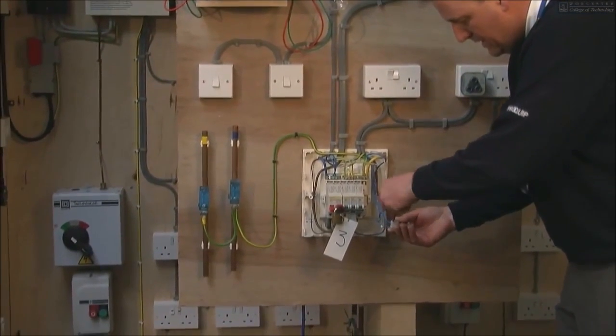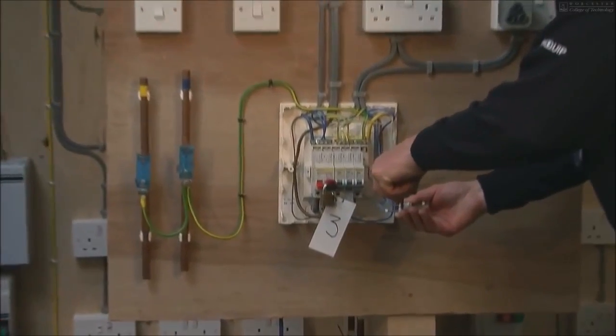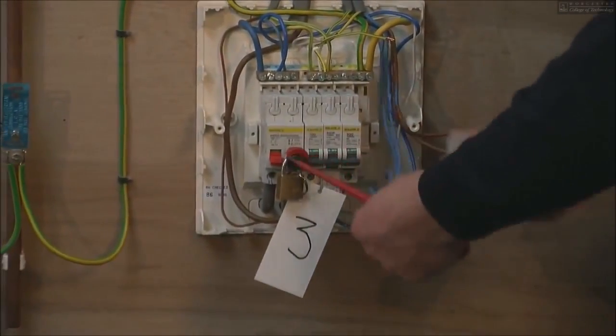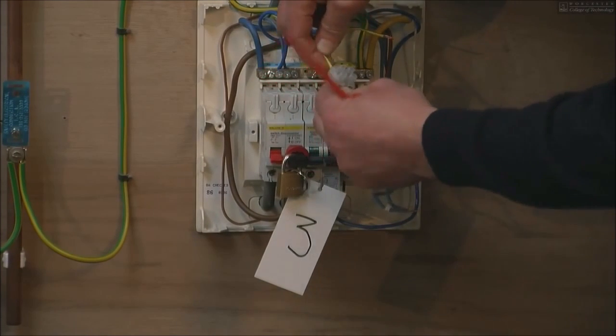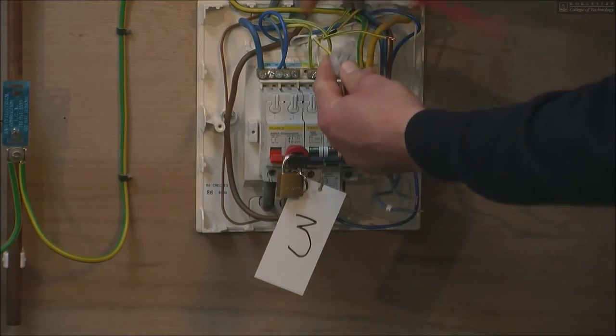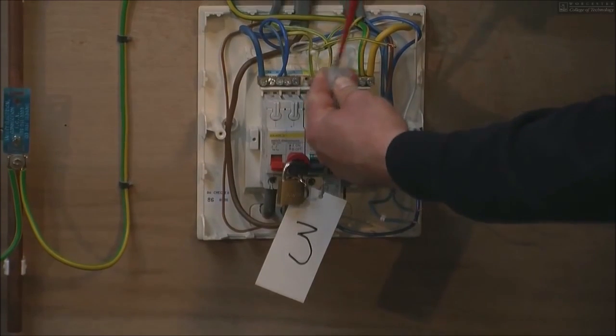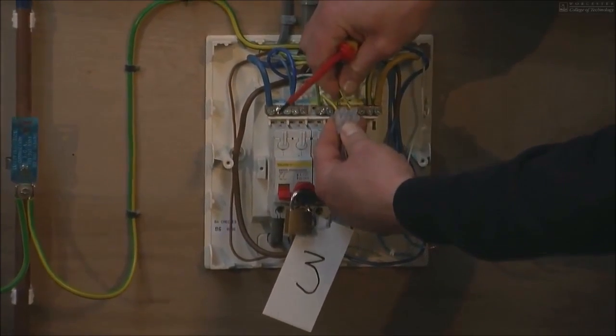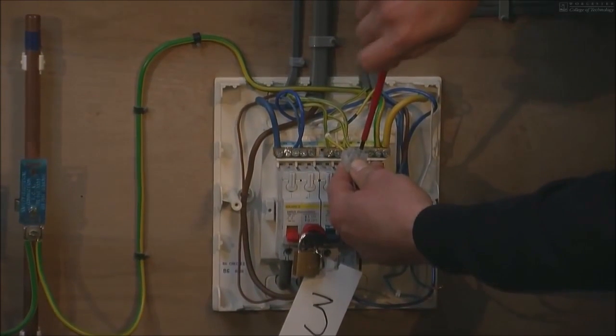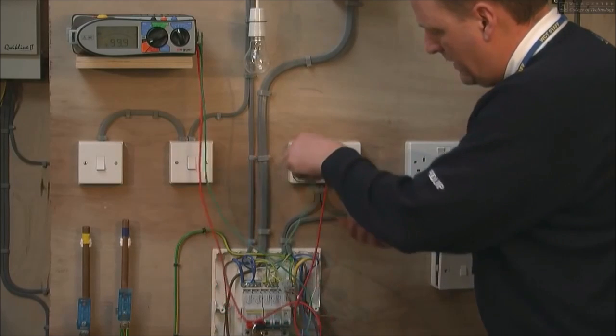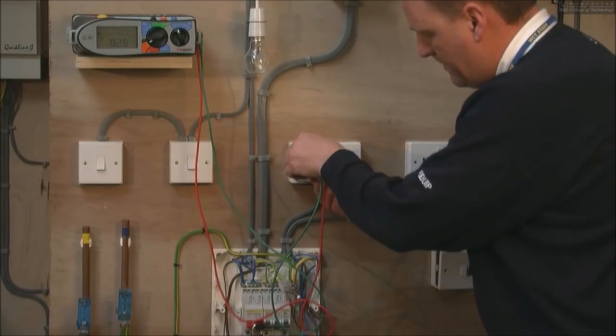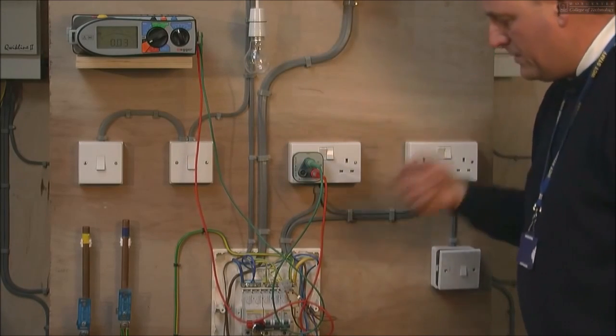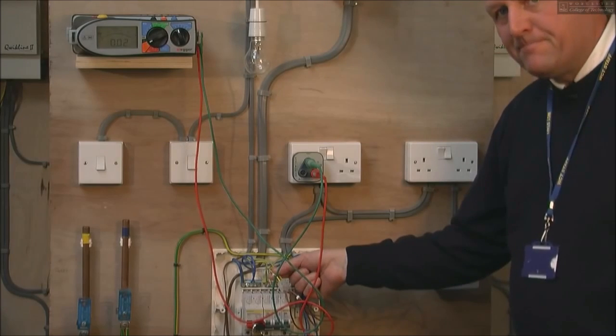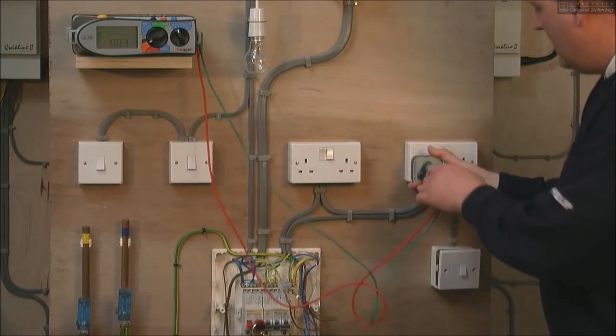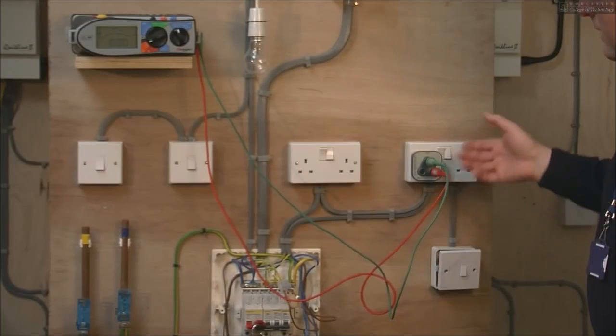Next thing we do is we remove the two neutral conductors. And we replace them with the CPC. Then go around to each of the sockets, and instead of going into the neutral this time, we go into the CPC. We start to get a reading. These readings are going to be slightly higher because we have a smaller conductor offering a higher resistance. We work our way around the ring circuit, and all our readings should be equal.